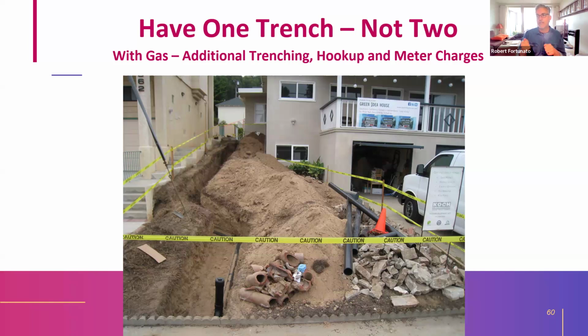We did the trenching in advance of the renovation. The advantage to that, which is sort of counterintuitive, is that we had a wall standing and could do all the trenching work and put in the new panel into the existing structure that would still have a frame. We were still using the same footprint of the building and knew where we wanted that new panel to go, but temporary power is very expensive from the utility.